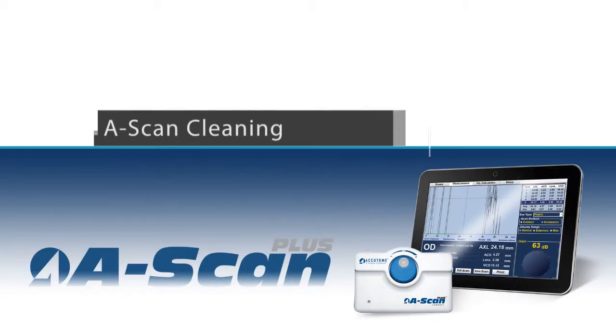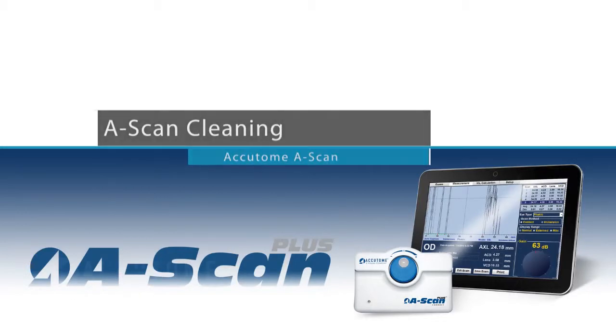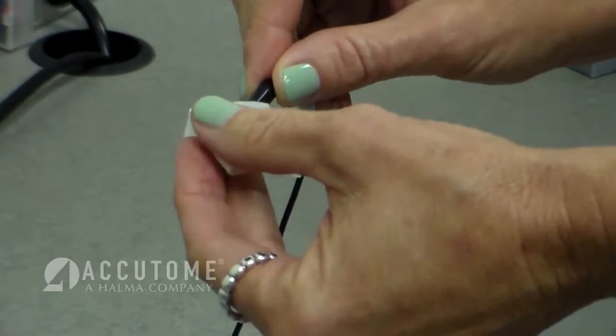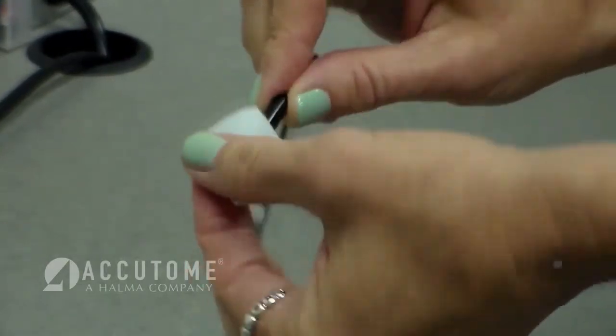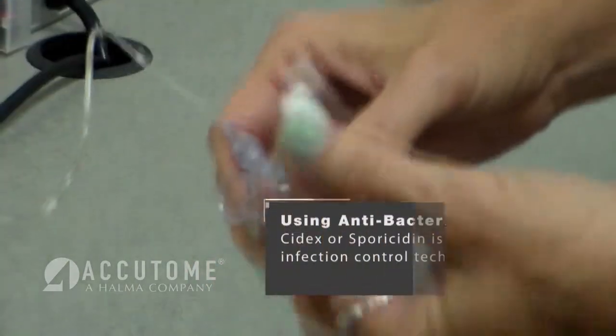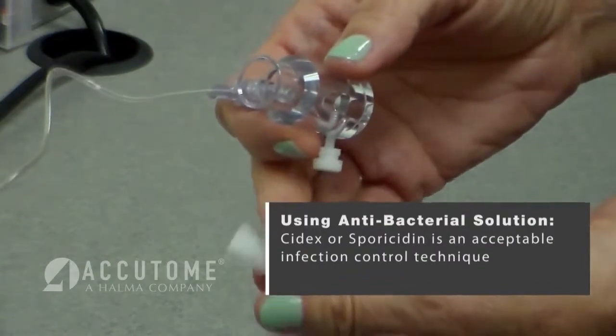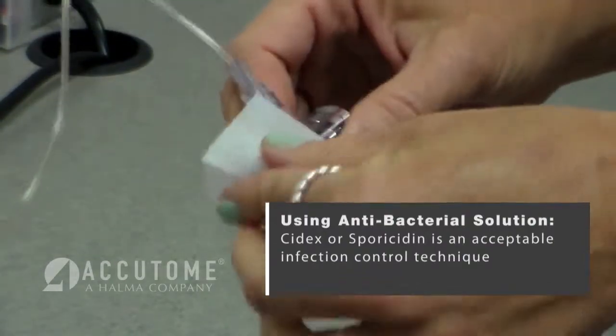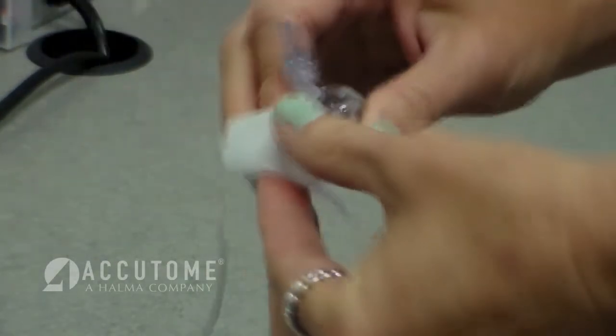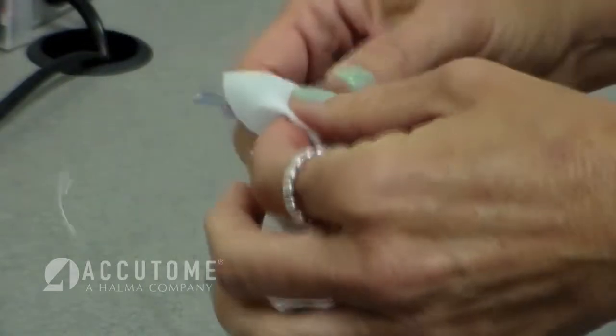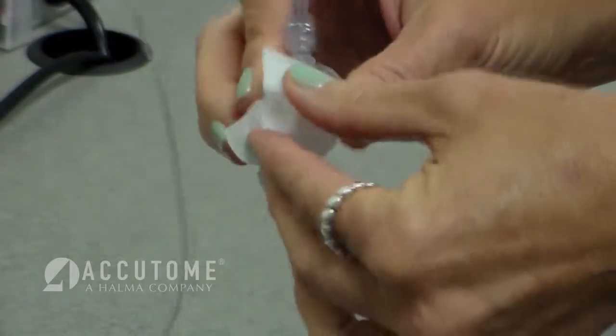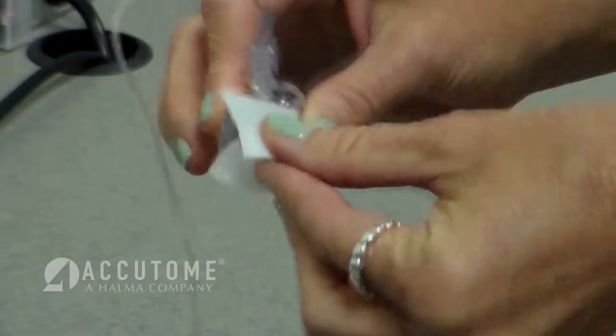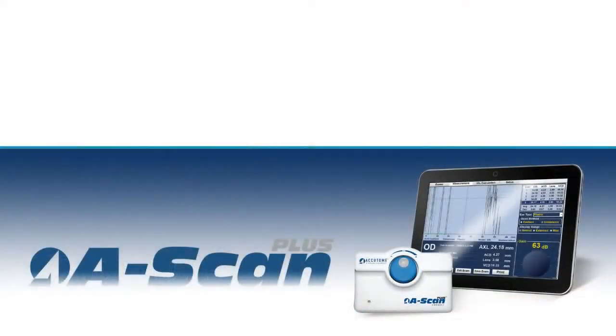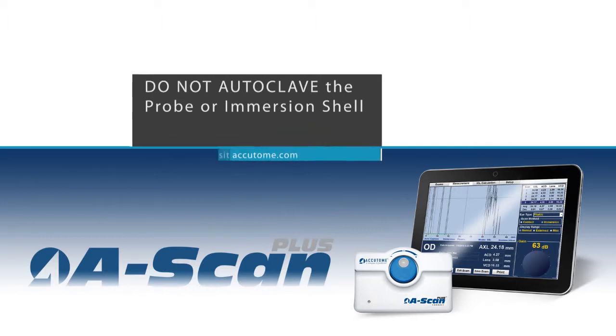Cleaning. Clean the A-Scan probe by wiping or soaking only the tip with alcohol. If a higher level of disinfection is required, an antibacterial solution such as Cidex or Sporicidin is an acceptable infection control technique. The immersion shell can be fully submersed in alcohol, Cidex, or Sporicidin. Do not autoclave either the probe or immersion shell.